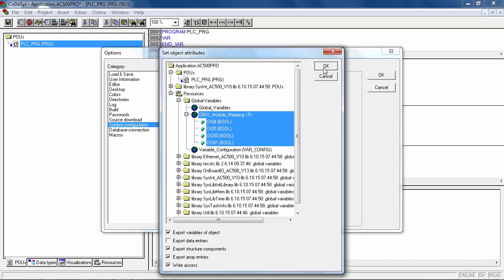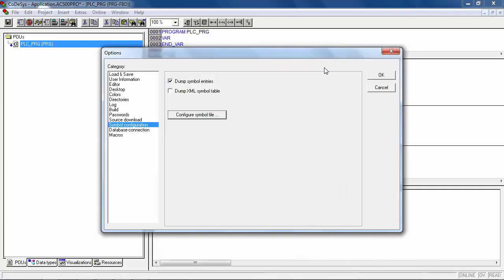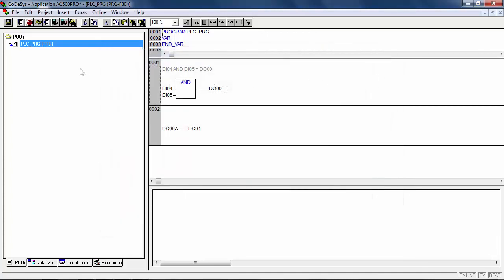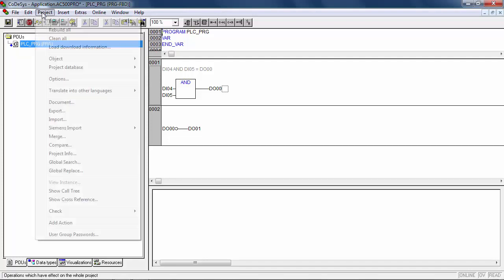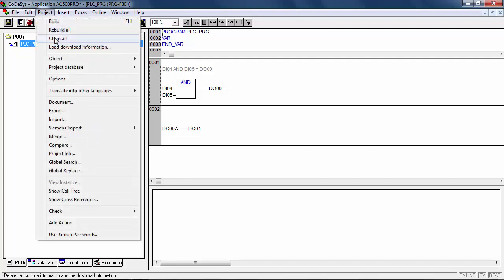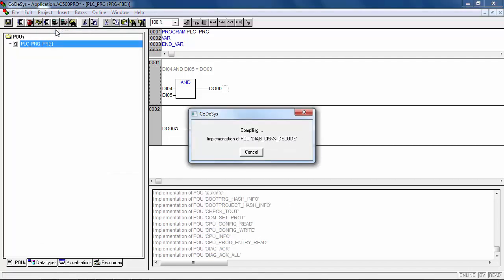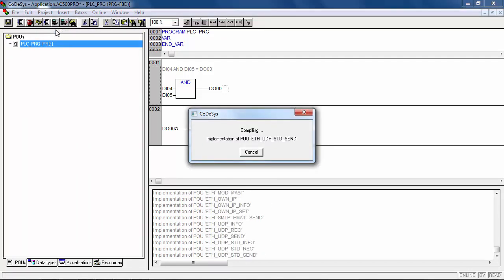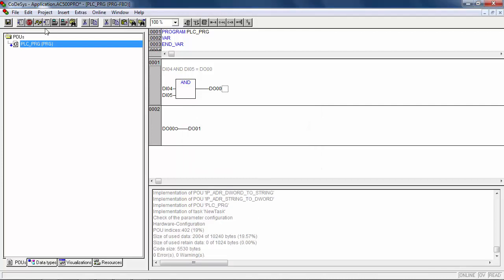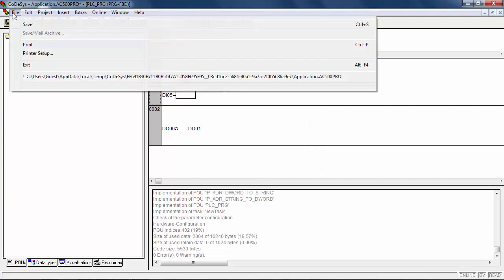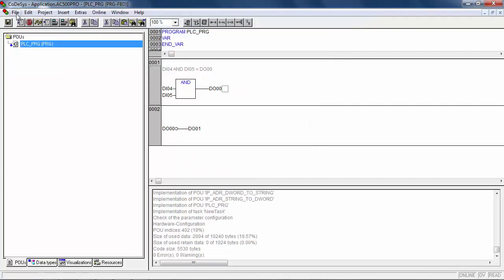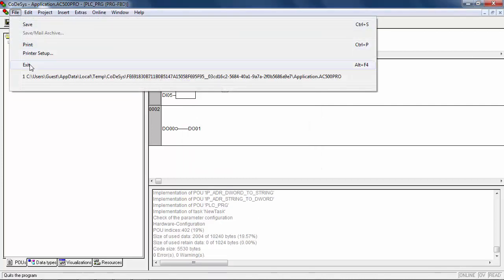In the end, close all windows by OK, and then realize a new compilation to regenerate the symbol file with new variables. Use Clean All and Rebuild All actions in Project menu. Pay attention, the symbol file has to be reconfigured only in case of variable renaming or addition of new variables.